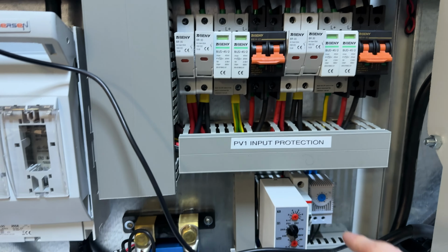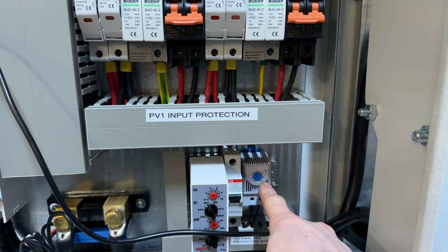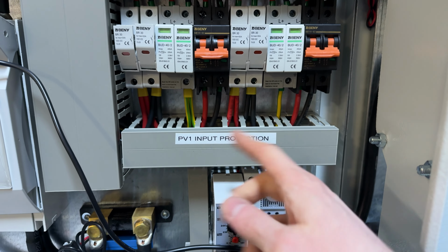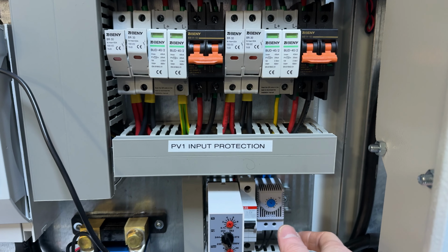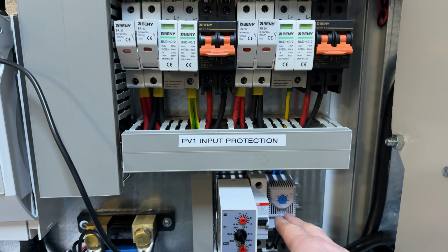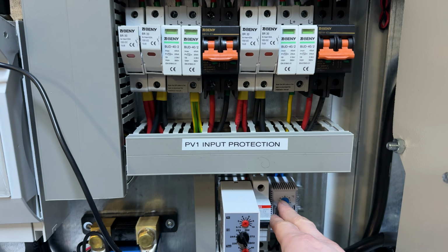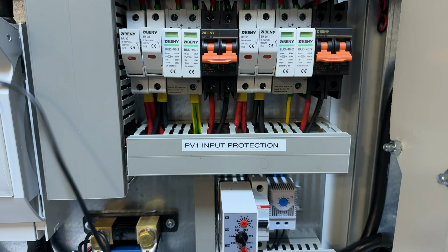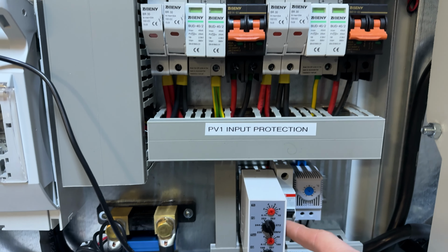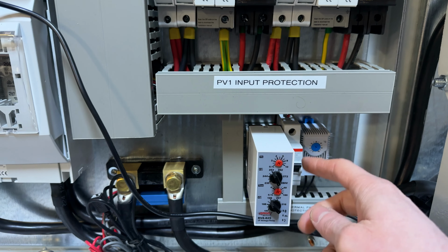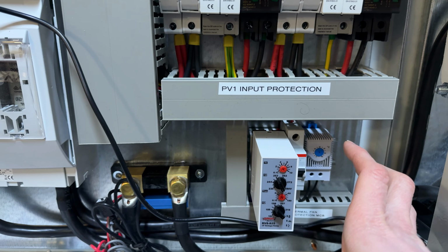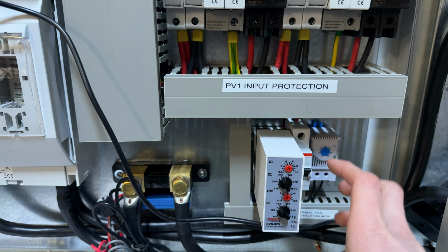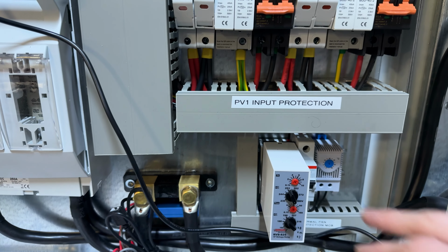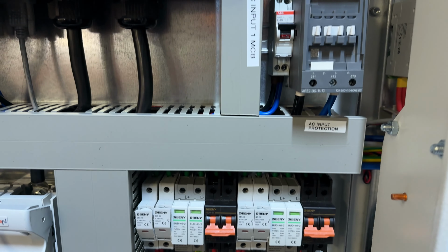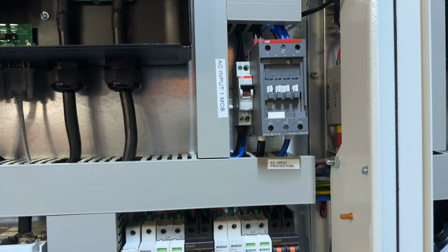Let's continue our guidance. This is a thermostat. It's going to start the cooling fan. If you operate the cabinet with the doors open, you don't have to worry about this. You can set the temperature to 25-30 degrees. This is a voltage and frequency relay. If there is an abnormal voltage or an abnormal frequency from the generator, this is going to deactivate the incoming power supply.